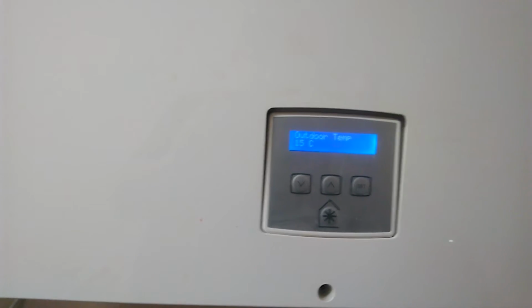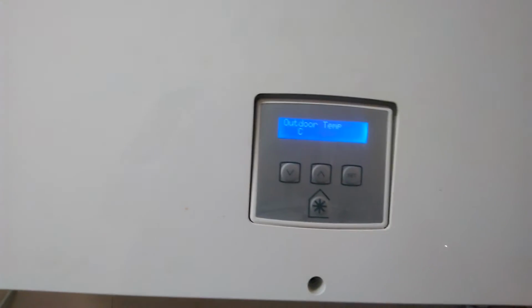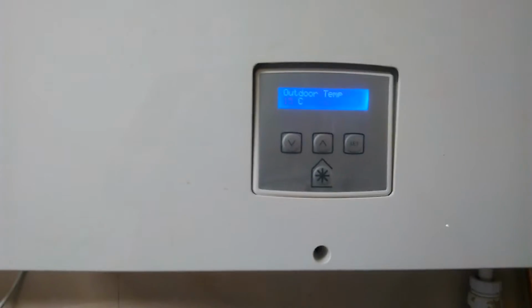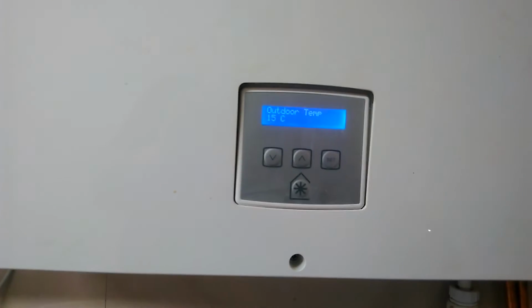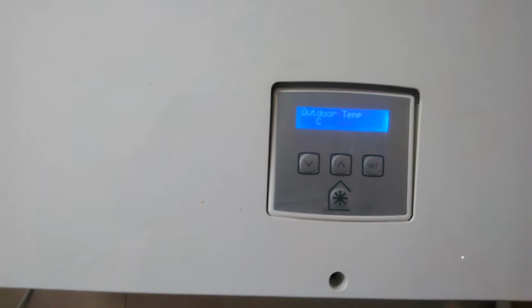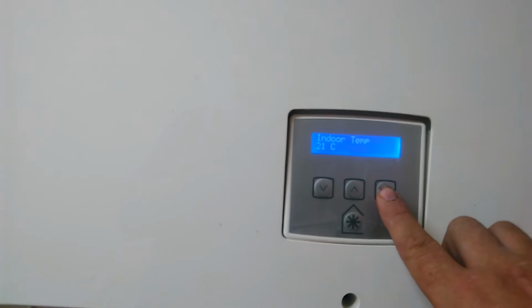External temperature is what you desire. We don't really want to be pulling freezing cold air in. Some people change this if they want cool air coming in, even during spring or even sometimes in winter if people have got a boiling house, but it's not recommended. The best sort of setting and window for the summer bypass to work in is between 15 and 21 or 22 degrees. Okay. So that's set at 21. That's set at 15. Okay, let's enter into the commissioning screens.